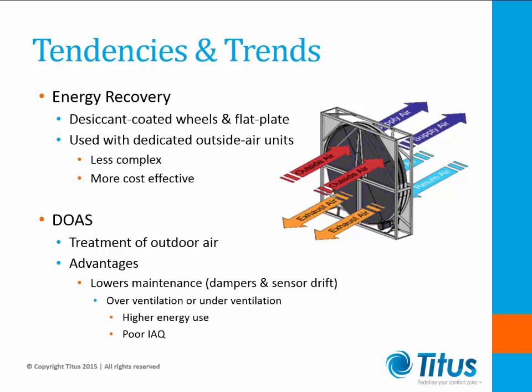Energy recovery is increasingly applied in air handling units and may be required by energy codes in certain applications having high percentages of outdoor air. Energy recovery enables incoming air to exchange heat and moisture with building exhaust air via desiccant-coated wheels. Successful application is dependent on many factors, most importantly climate. It is generally easiest and most cost-effective to apply when dedicated outside air units are used.